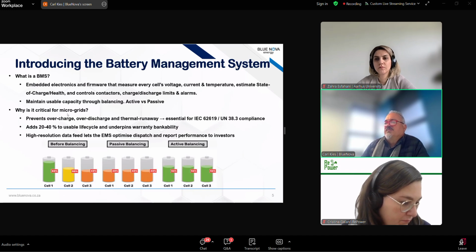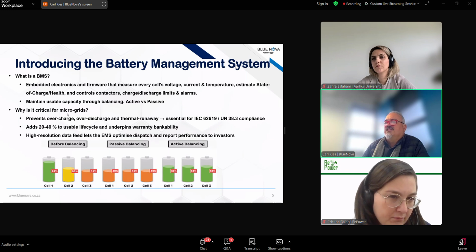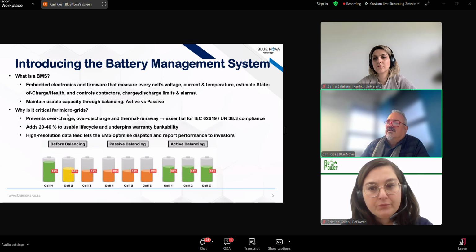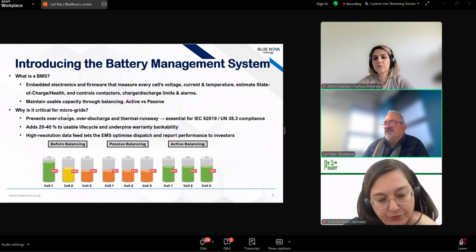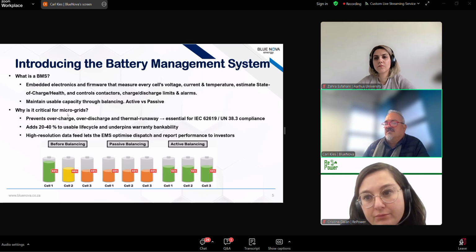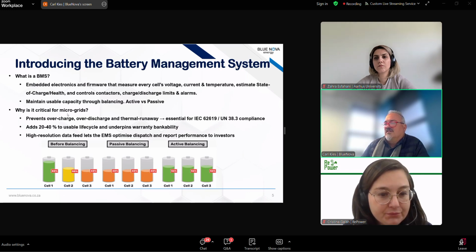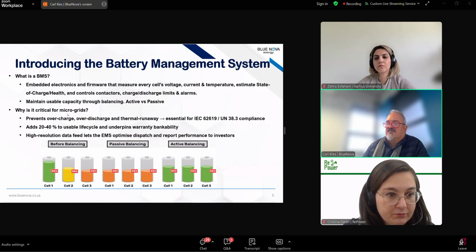Here's a quick indication of the difference between active and passive balancing. This is a worst-case scenario: say in this battery you've got cell 1 at 80%, cell 2 at 50%, and cell 3 at 40%. If cell 3 gets to 0, the battery will technically be empty, but you still have 40% capacity in cell 1 that you can't use. Passive balancing effectively gives you the average of the lowest cell in the pack, so that's not very efficient - you end up wasting energy in that balancing. Whereas with active balancing, you get the average capacity of the pack spread amongst all the cells if it works correctly, resulting in more energy efficiency and higher yield on your investment.